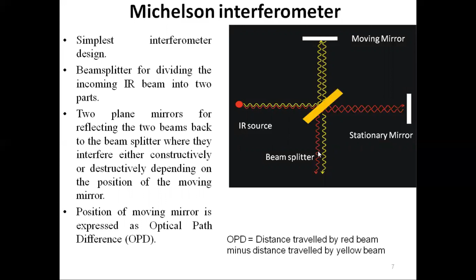The interferometer has a simple design: a beam splitter for dividing the incoming IR beam into two parts, and two plane mirrors for reflecting the two beams back to the beam splitter, where they interfere either constructively or destructively depending on the position of the moving mirror. The position of the moving mirror is expressed as optical path difference, OPD. In this diagram, the radiation coming from the IR source is split into two parts by the beam splitter. One goes to the stationary mirror and the other goes to the moving mirror. After coming back from these two mirrors, the radiation goes towards the sample.